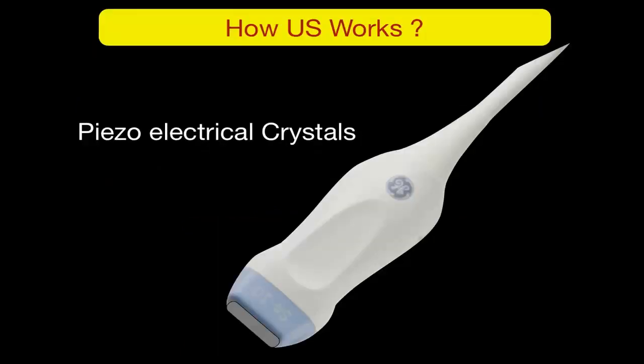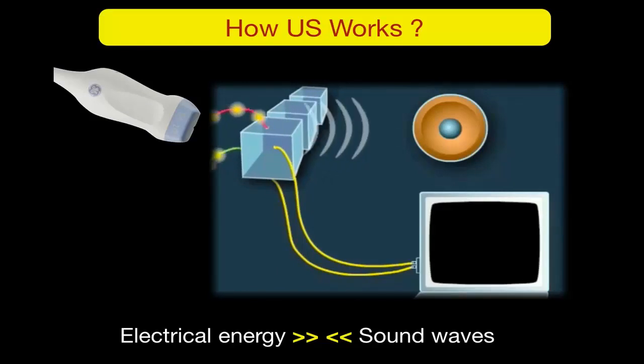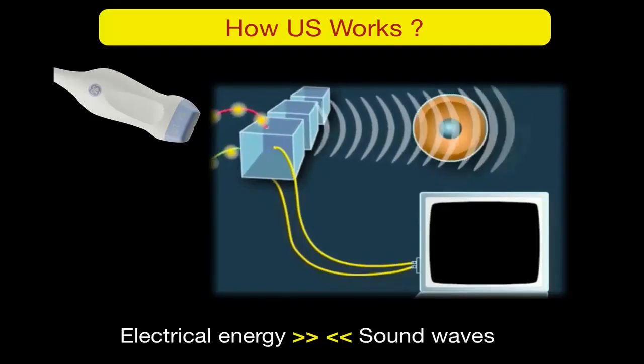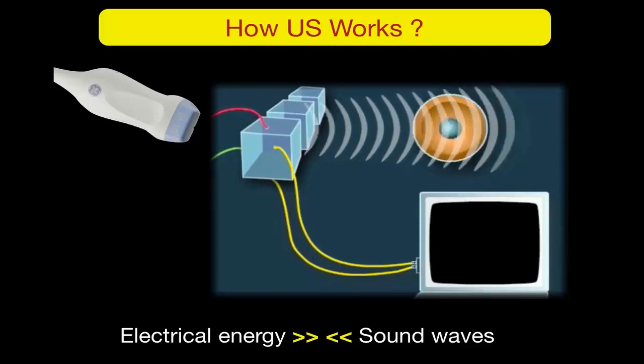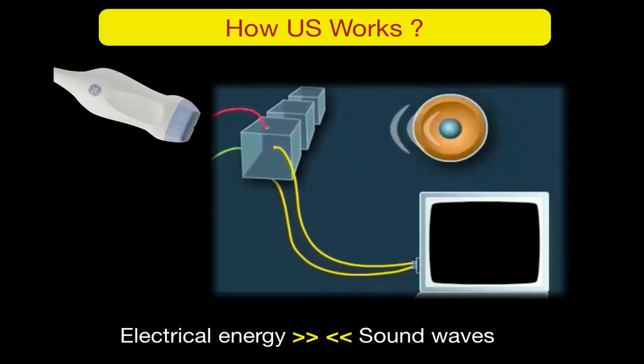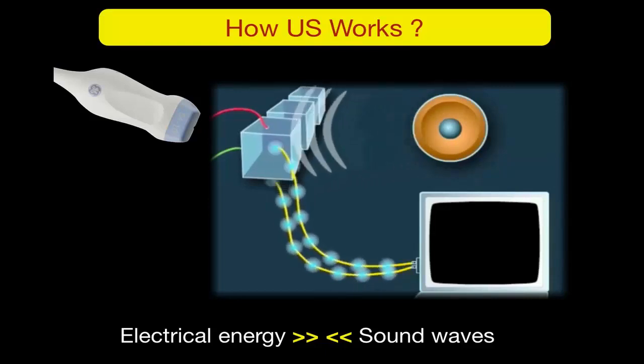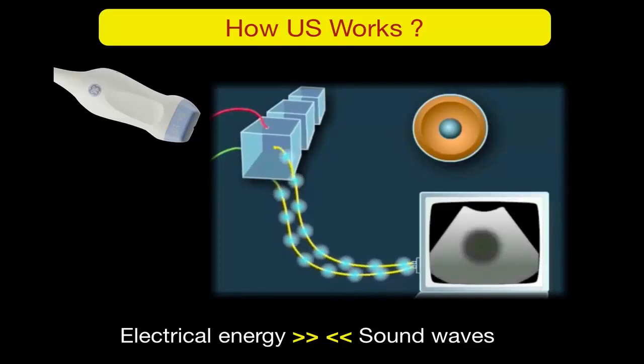The key to how ultrasound works is the piezoelectric crystal located at the tip of the ultrasound probe. These crystals convert electrical energy into sound waves and vice versa. The probe receives electricity from the machine, the crystal converts it into a sound wave and sends it to the object. Depending on the type of object, some sound bounces back to the probe, which converts it into electrical signals sent to the screen, where the object is plotted.